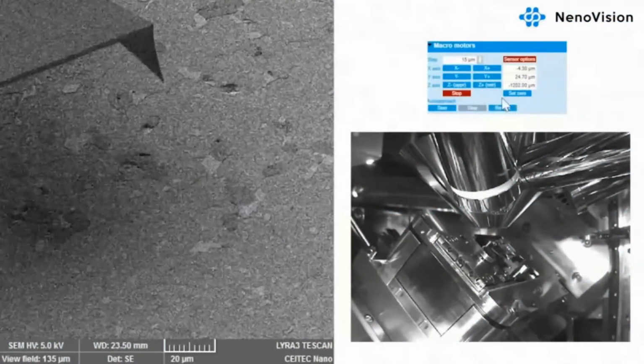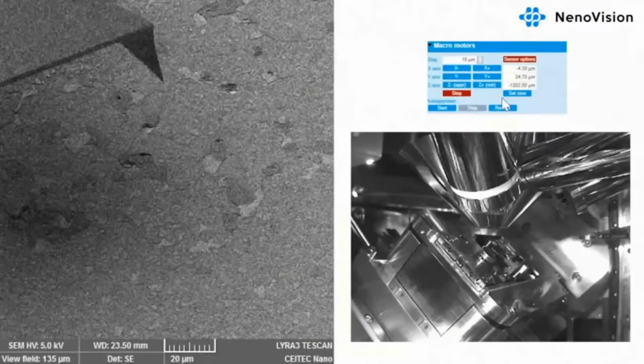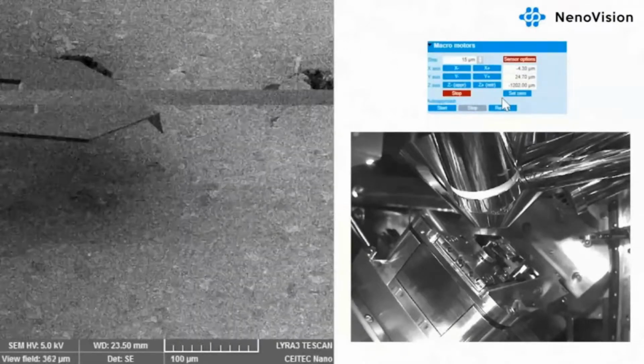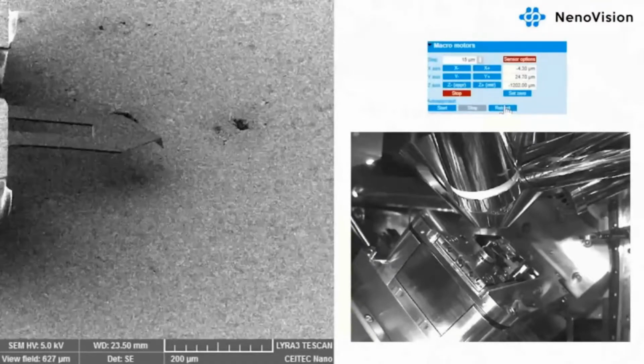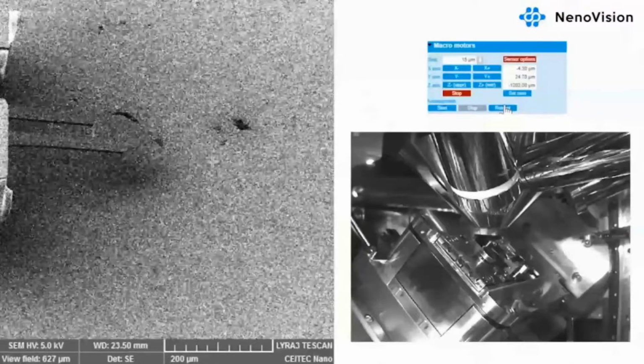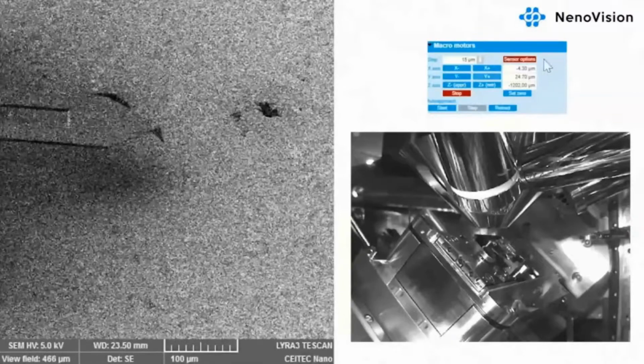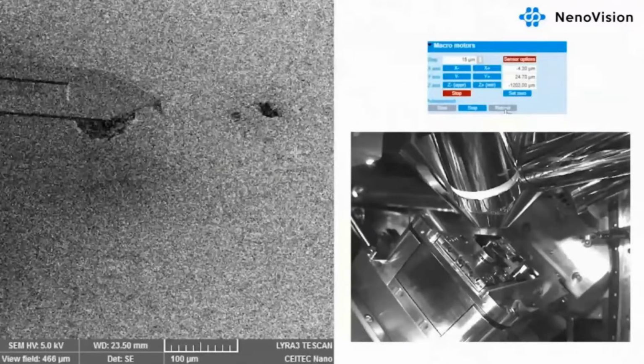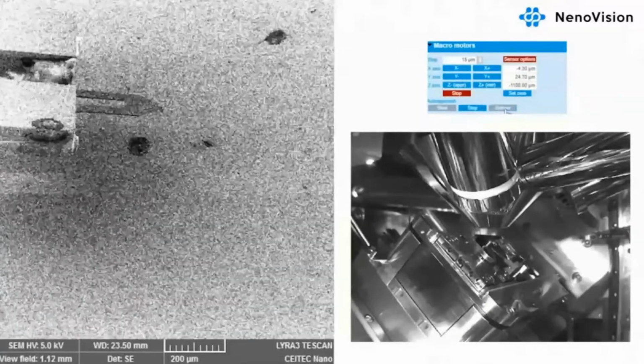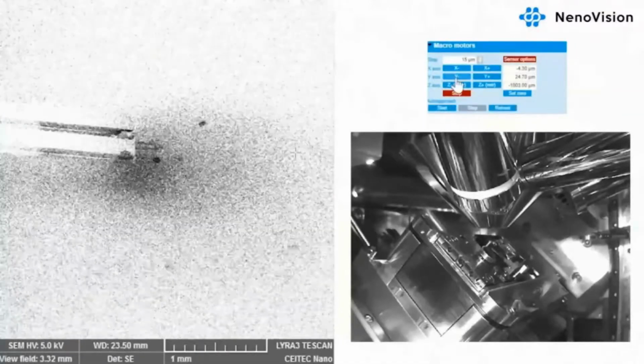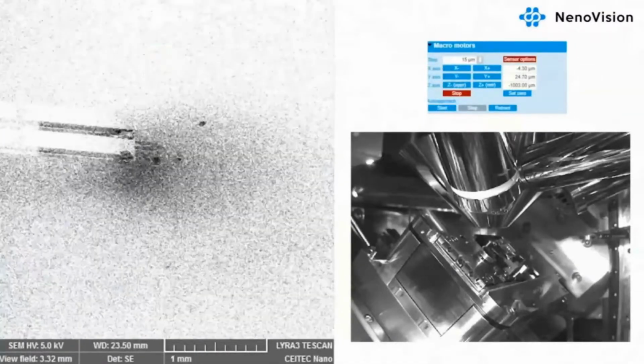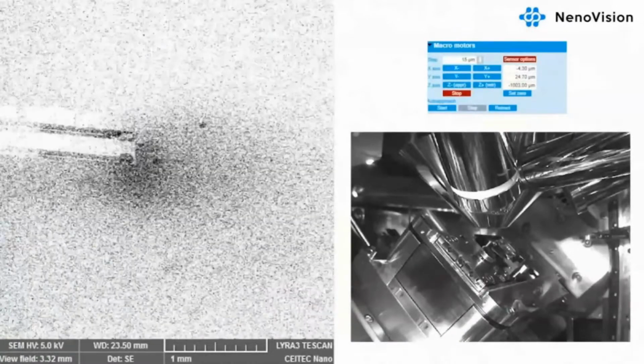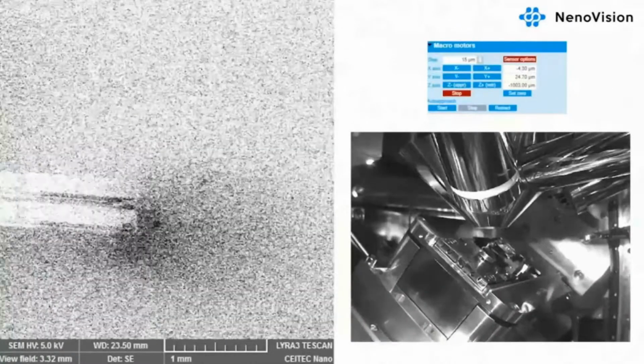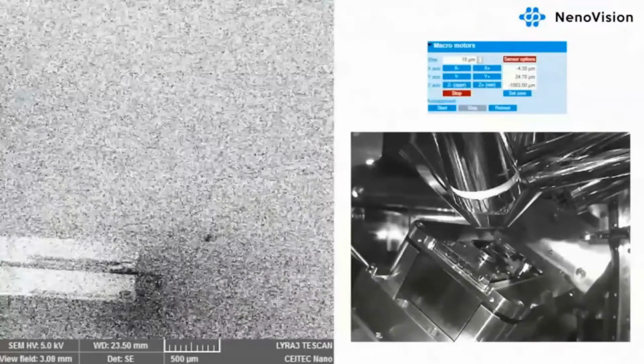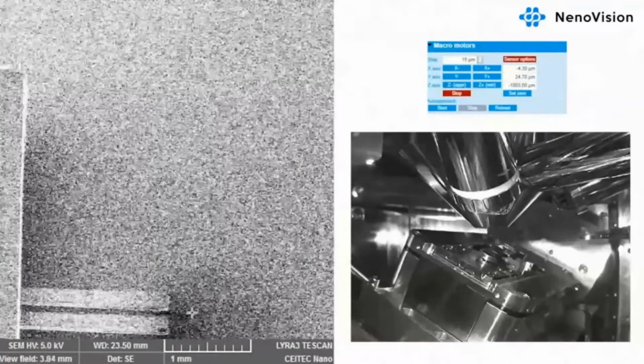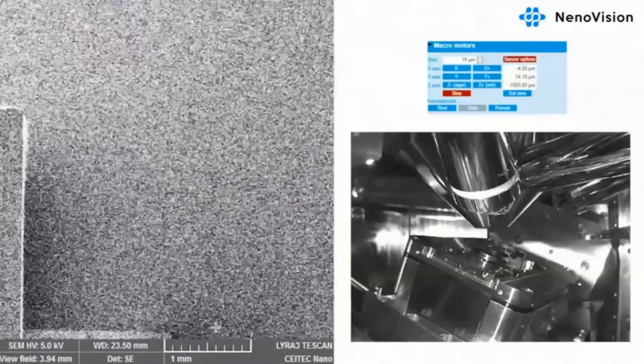After the measurement, I tilted the stage for better visibility, and we retract the tip with a retract button. In this case, the macromotor moves with 50 micrometer step away from the sample surface. As we zoom out and we are pretty far away from the sample surface, I tilt the stage back to 0 degrees. You can watch the tilting of LiteScope in the right part of the slide.